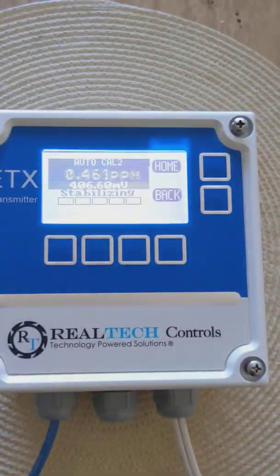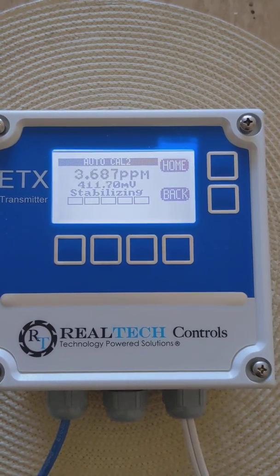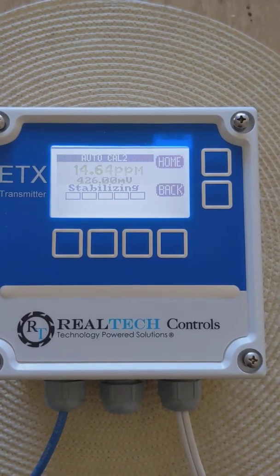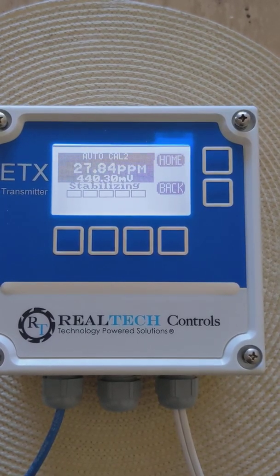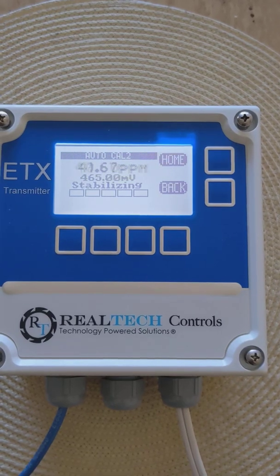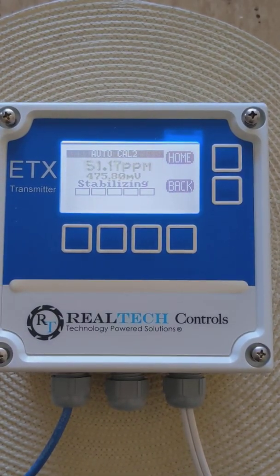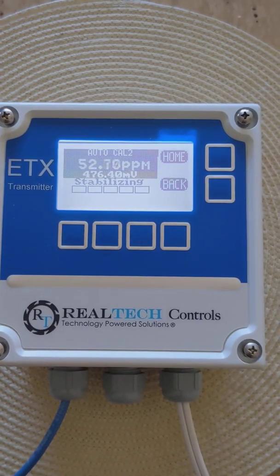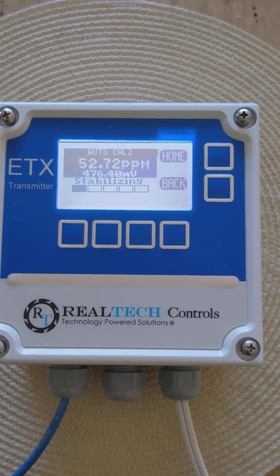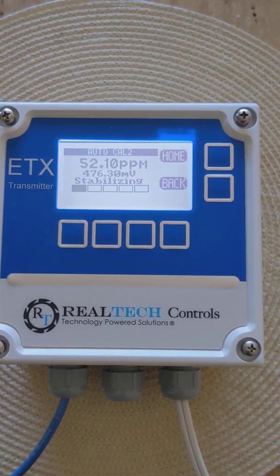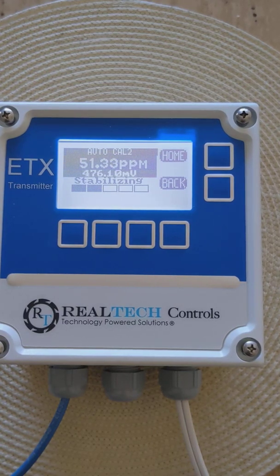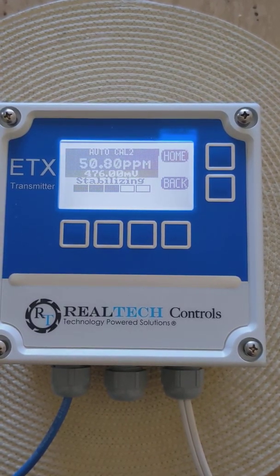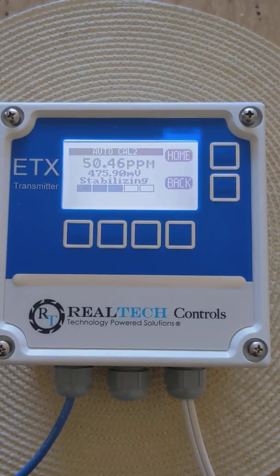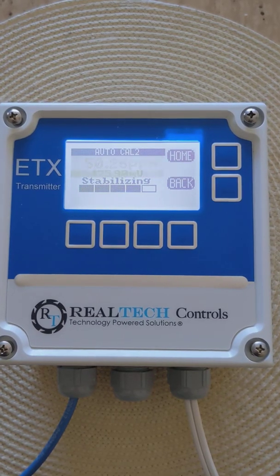And now I will take this, rinse it off, and I will put it in the city water solution again. And you wait for that to stabilize. And so, for instance, I had this in a 100 ppm solution. We'll see if the controller recognizes that I'd like to do a 100 ppm calibration. It probably won't. And then we can change that manually to make it whatever buffer solution we have the sensor in.